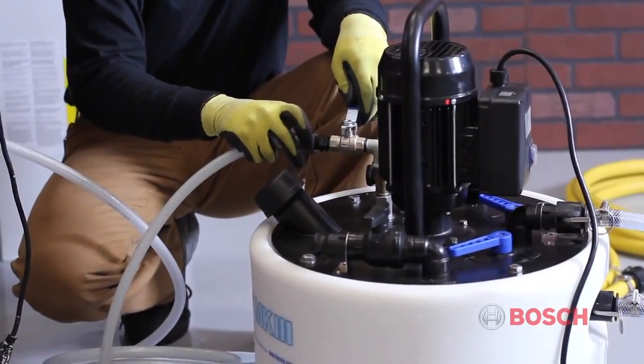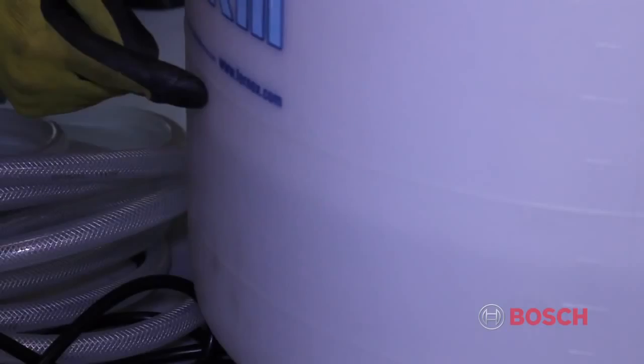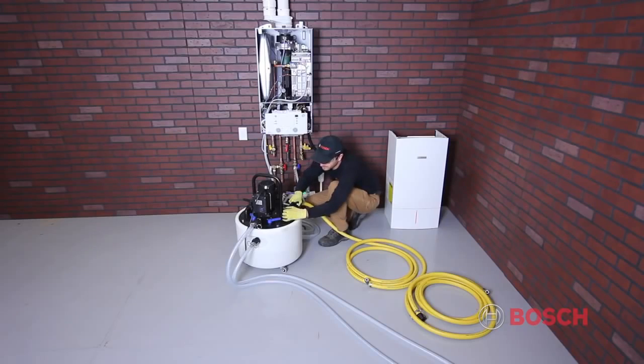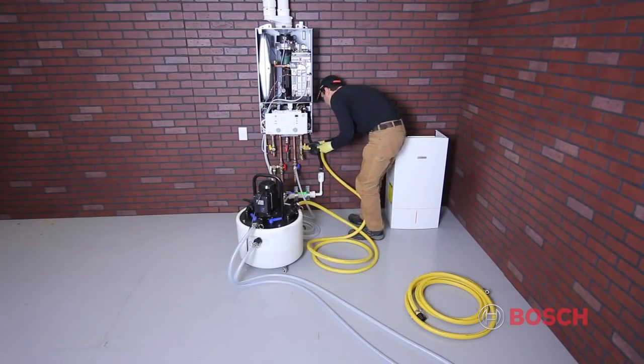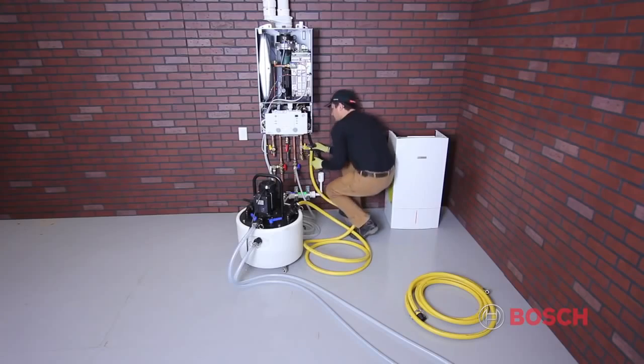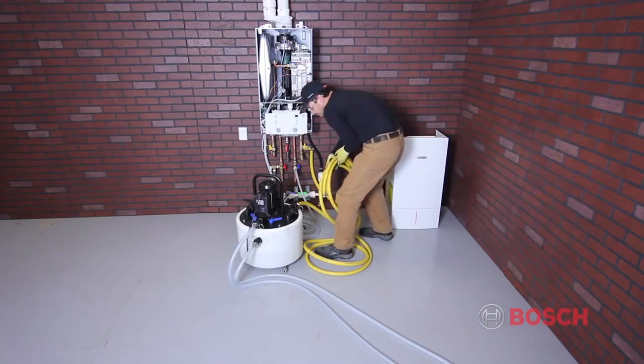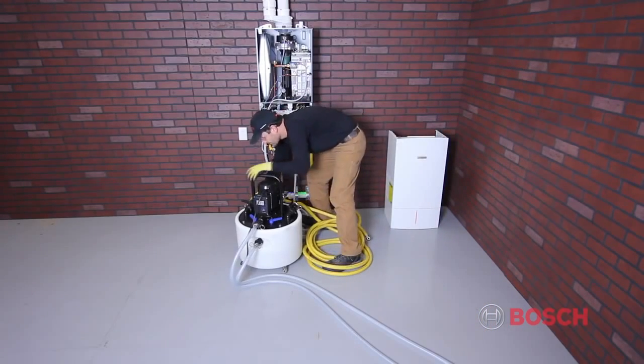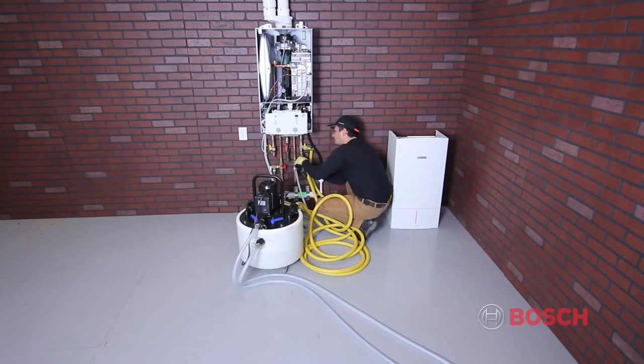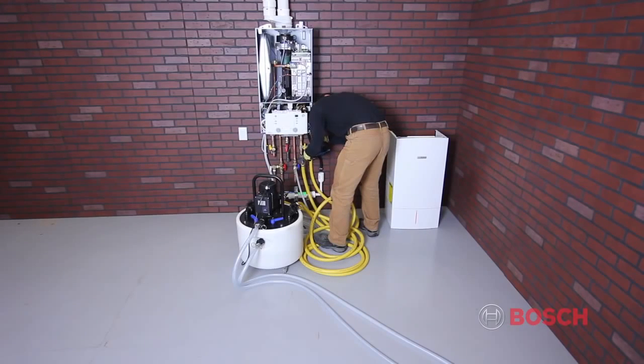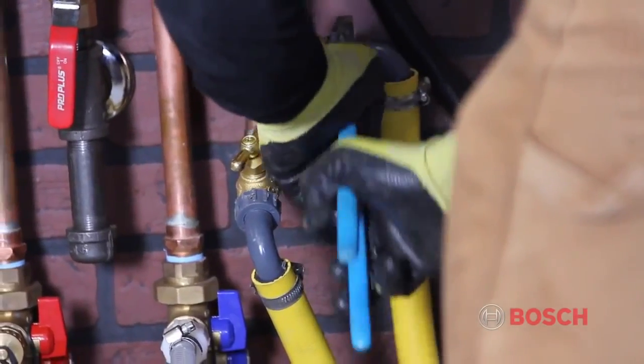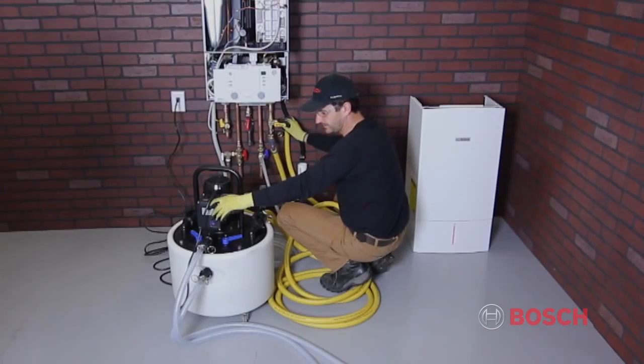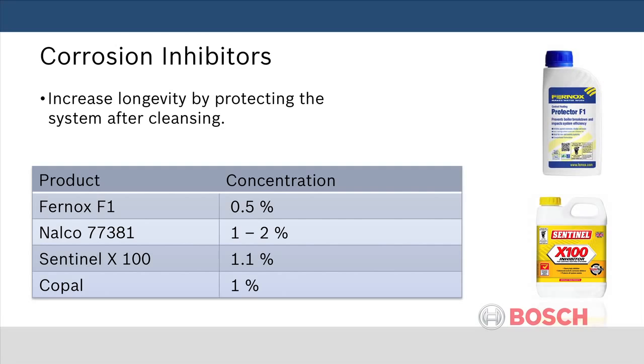When using a chemical cleaner, make sure to follow directions provided by the manufacturer in regard to usage and, if necessary, disposal. Only use chemicals that have been approved for use with the Greenstar boiler. For more information, refer to Section 5.1 of the installation manual. When using a pump flushing system, make sure to connect all hoses and follow the pump manufacturer's instructions in regards to fill levels and flow direction. Once the system has been cleaned, add the inhibitor package following the manufacturer's instructions. The following anti-corrosion inhibitors and concentrations are approved for use with the Greenstar boiler.